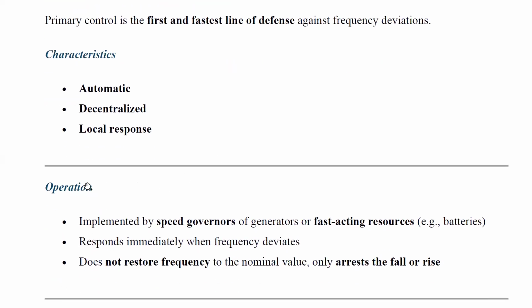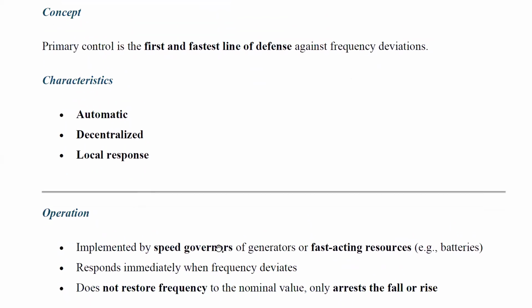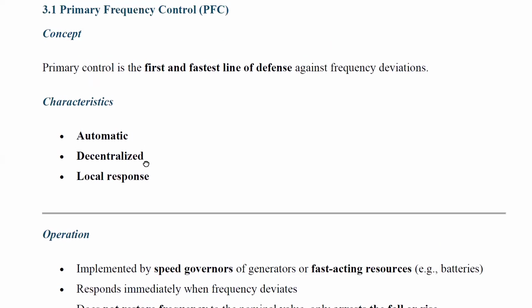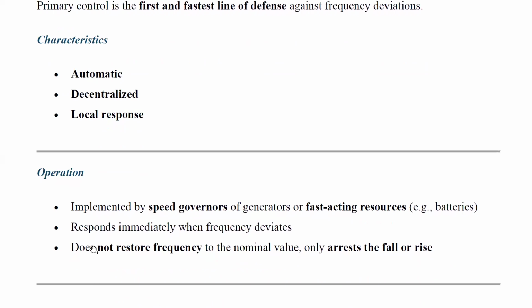In operation, primary frequency control is implemented by the speed governors of the generators, or otherwise by fast-acting resources, that means battery backup. Immediately it will act in the system such that the frequency is maintained constant. It responds immediately when the frequency deviates. It does not restore the frequency to the nominal value, it only arrests the fall or rise. That is all it will maintain.